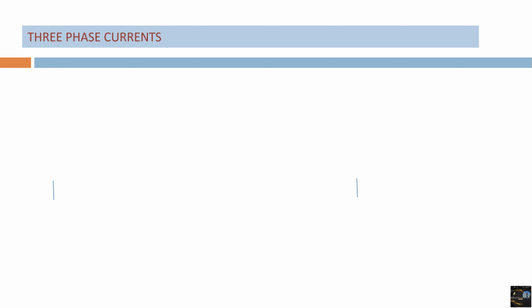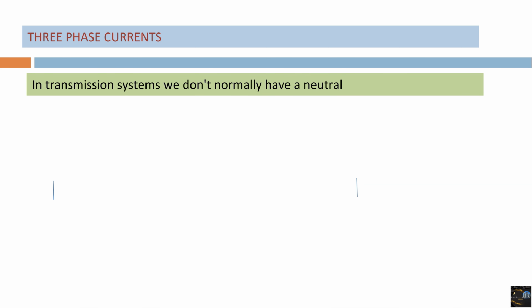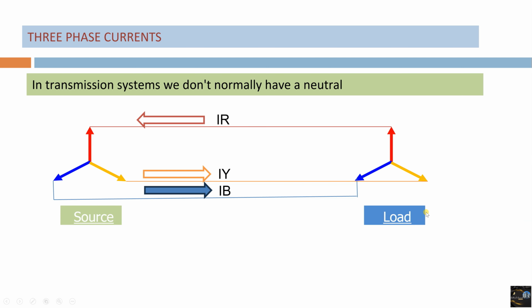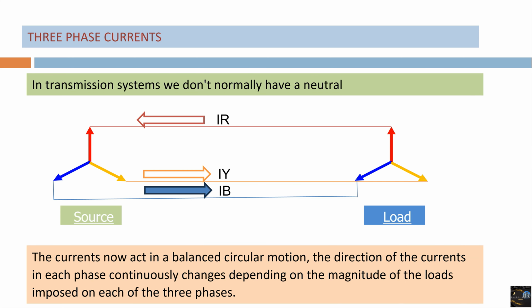But in our three-phase transmission line, we don't normally have a neutral. Let's see a scheme. Normally in our transmission line, we have only three phases. The currents now act in a balanced circular motion. The direction of the currents in each phase continuously changes depending on the magnitude of the loads imposed on each of the three phases. For the transmission system, all we are doing is taking power from the source and it's going towards the destination. And we don't need phase to neutral voltages. There is therefore no point paying for a neutral conductor and we have a TP system.